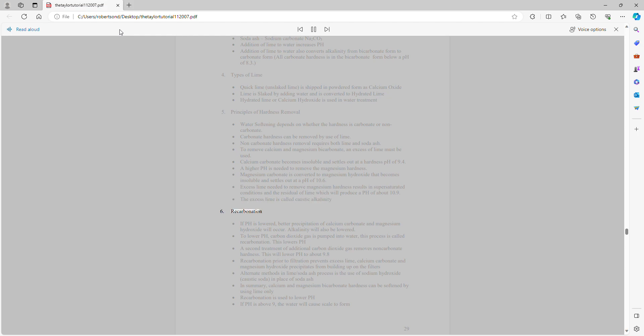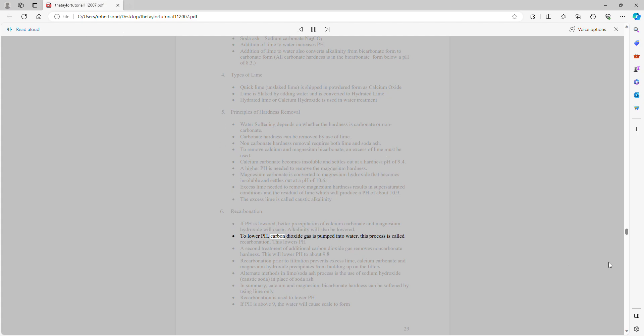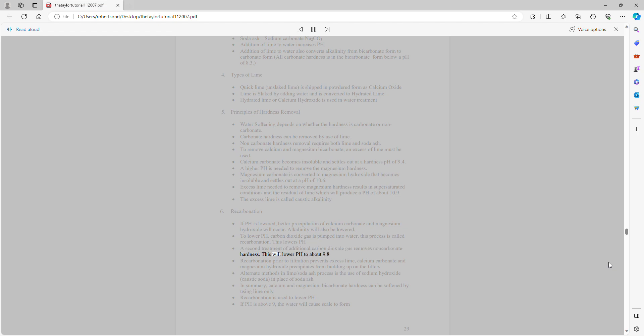Recarbonation: If pH is lowered, better precipitation of calcium carbonate and magnesium hydroxide will occur. Alkalinity will also be lowered. To lower pH, carbon dioxide gas is pumped into water. This process is called recarbonation. A second treatment of additional carbon dioxide gas removes noncarbonate hardness, lowering pH to about 9.8.